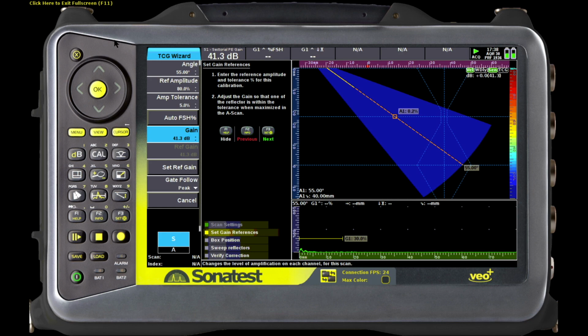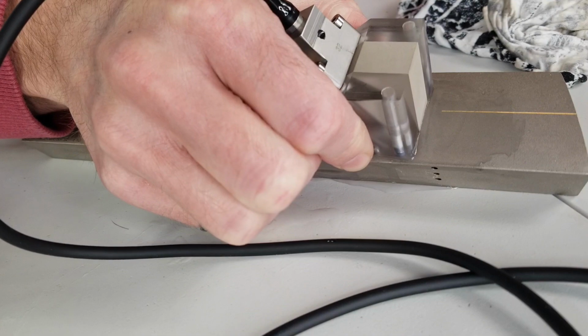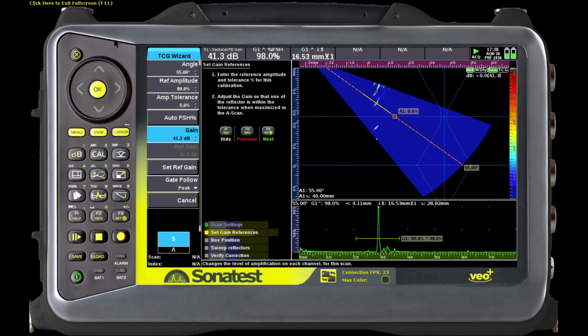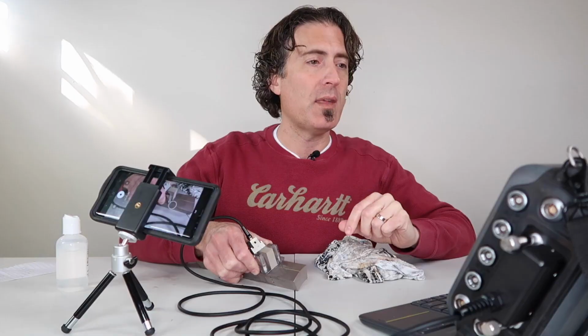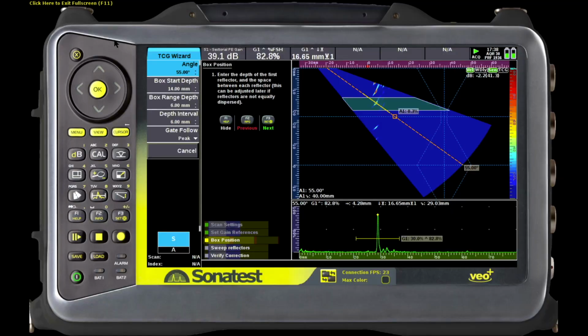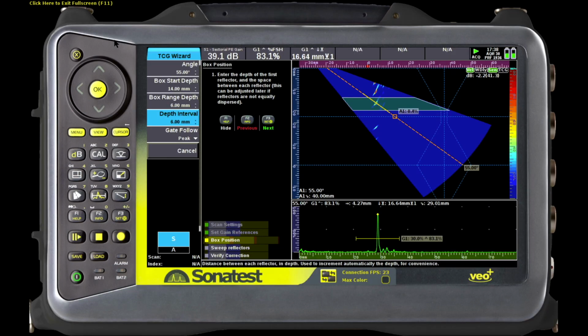And then there's a gain setting here, and we use that just to ensure that that first reference reflector that we're using, which should be the loudest one, is at about 80%. You see here it is a little hot. So it just makes it easier if we take that down to 80% to start. And then on a VEO, you have a calibration box that spans the width of the S scan. On an OmniScan, you'd use your gates, of course. And our box start, we can move that up and down. And the box range depth is the size of the box. And the depth interval, every time we move to the next reflector, it just bumps it down by how many millimeters. In this case, I'm going to use 6.